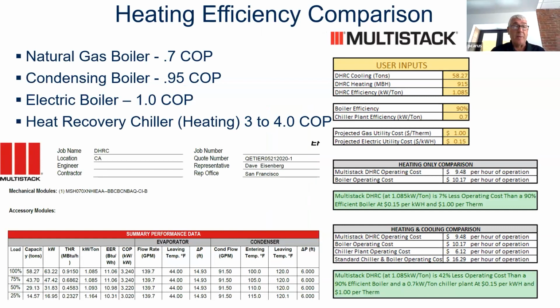Everybody wants to know what's my payback and what kind of savings can I get using some different coefficients of performance and some capabilities. We can look at a natural gas boiler, condensing boiler in this spreadsheet. And for the interest of time, I'll just describe what we're looking at. You've got some user inputs, some utility costs, some sizes. Once you plug in the data, it will tell you in the green areas how efficient that particular machine is.